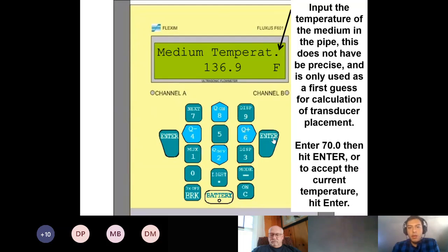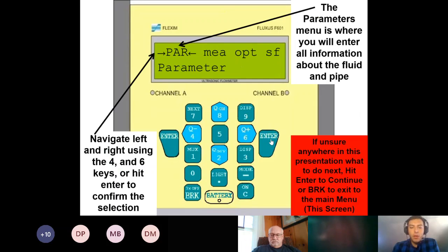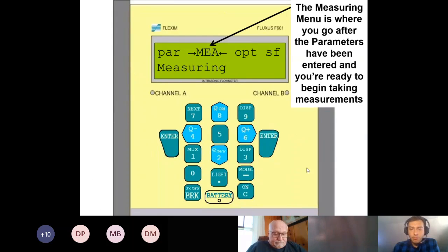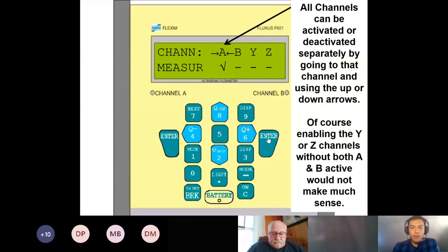Medium temperature, just try to get this as close as possible. If the temperature fluctuates, make sure you're getting the average of them. Basically, this is going to affect the spacing of the transducers, though. And that's all the parameters that you need to put in. Once you finish putting in your parameters, go over to measurement, and you're ready to start taking measurements.